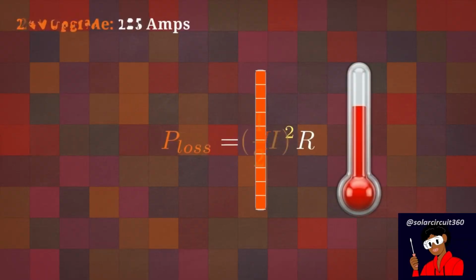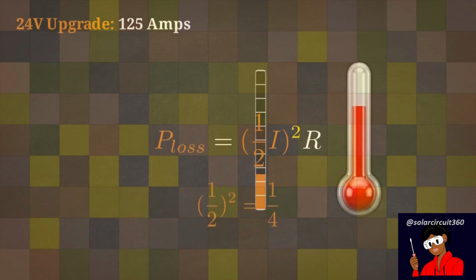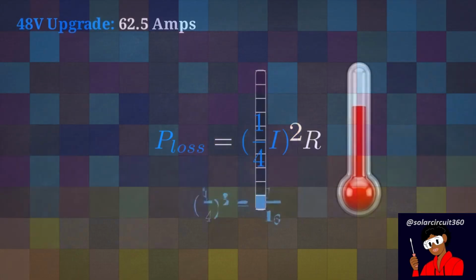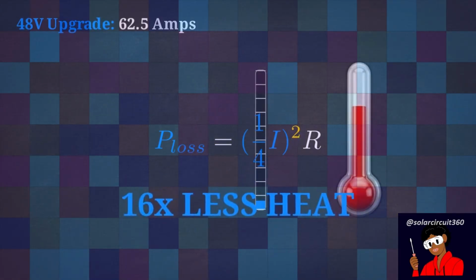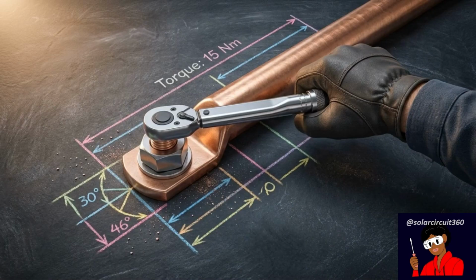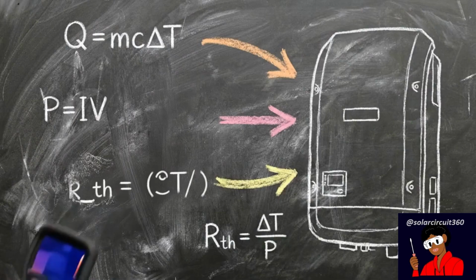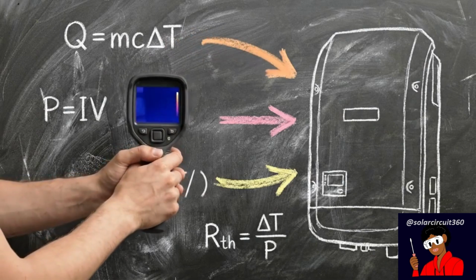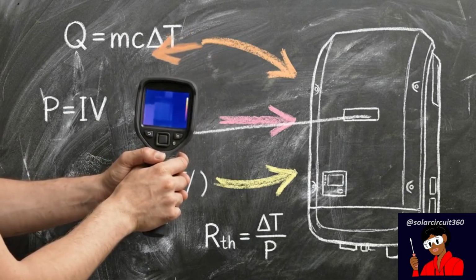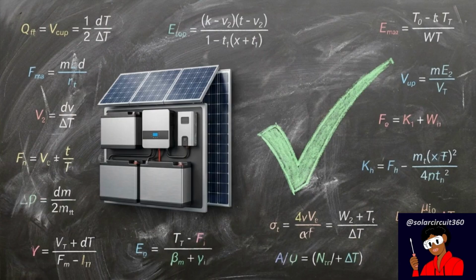Applying this to a 24-volt upgrade, cutting current in half drops thermal stress by a factor of 4. Taking the final step to 48 volts quarters the 250 amp load to 62.5 amps. Squaring that reduction reveals the 48-volt system generates 16 times less heat. This exact mathematical reduction is what allows builders to clear the extreme thermal bottlenecks found at the lugs, breakers, and busbars of 12-volt systems. Professional installers validate this drop in component stress continuously in the field, using clamp meters and thermal imaging cameras. Upgrading to 48 volts mathematically bypasses the geometric penalty of thermal physics.